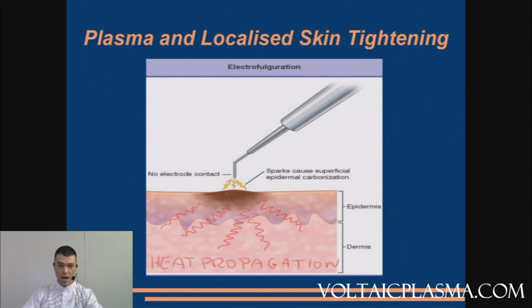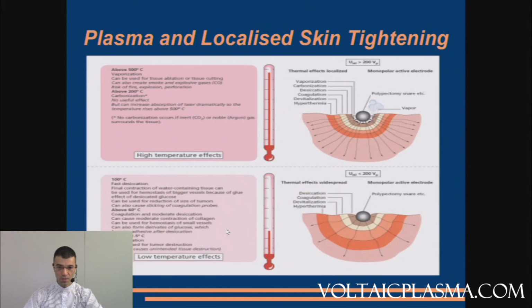So, for example, if you have a level 1 or 3 battery configuration and you apply it for half a second, or you apply it for 1 second, then obviously if you apply it for 1 second, the amount of heat released is much higher than for half a second. It's just because that heat is propagated for the length of time that you have applied the arc. So this is one important concept.